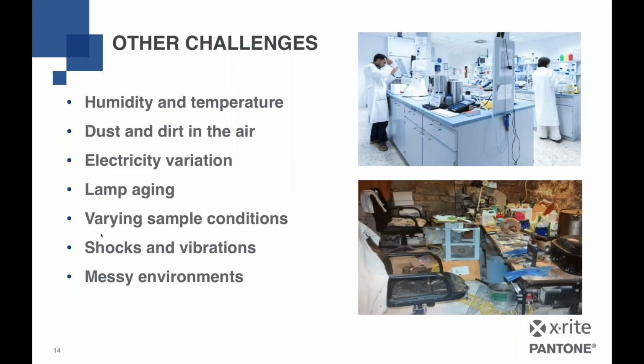Now, other challenges with instruments are, of course, of an environmental nature. Humidity and temperature are always an issue. Dust and dirt in the air. Electricity variation is still an issue in some regions of the world. Lamp aging of the instrument itself, and varying sample conditions, is a general issue which needs to be controlled separately. Then, of course, shocks and vibrations might harm an instrument of optical nature because you have optical paths which need to stay consistent and stable.